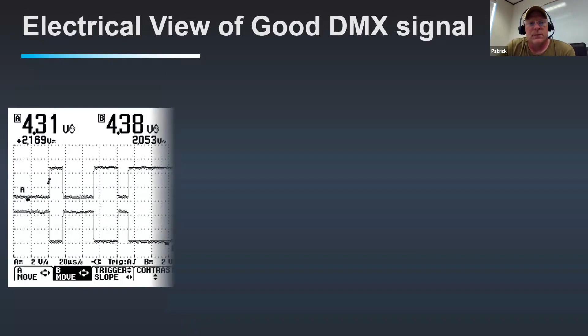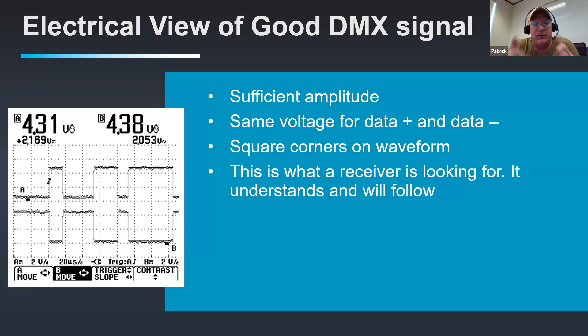Here's what that view looks like - this is the plus and minus. You have the plus 5 volts and the minus 5 volts, and you can see them equally opposing each other. That way, any interference that appears on the cable is equal on both and gets counteracted, so it doesn't really happen. The amplitude - that spike, the upward or lower part - needs to be of sufficient amplitude, and it should be the same for both plus and minus. This is a scope shot - don't try to analyze what it actually means, just look at the electrical characteristics of the signal: nice, sharp corners, up, straight down. All that matters when you're talking about the number of times it's sending ones and zeros in a given second.